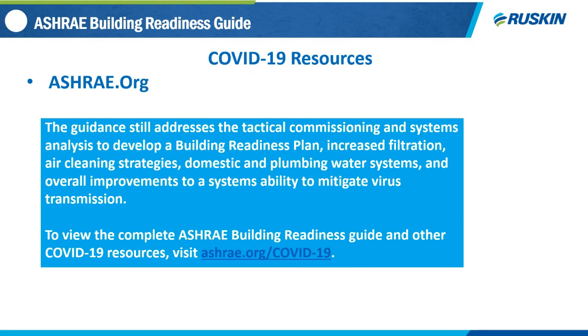What I was addressing is during normal operation for most systems, in order to maintain the minimum ventilation rates required for the space, you only need to ventilate that space when it's occupied. And what we're talking about here is during this pandemic, maybe it makes sense to run that system 24/7, especially if you're not able to increase the outside air intake through the day, which would be ideal. Really, that's what you want to be doing. But I hope I've answered that question. Right, I think it did.